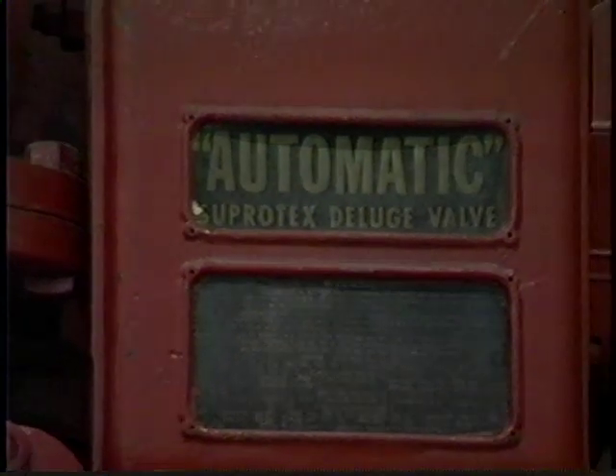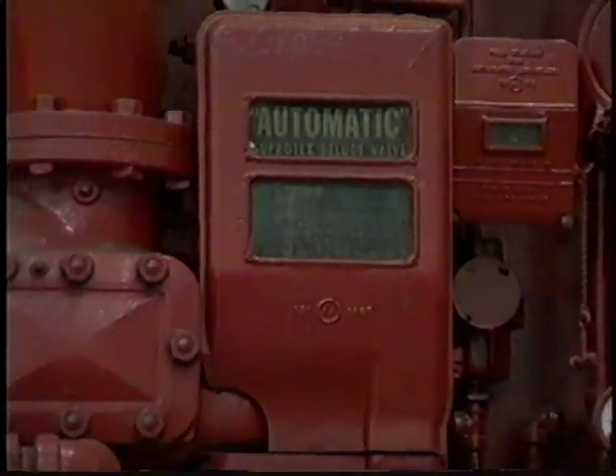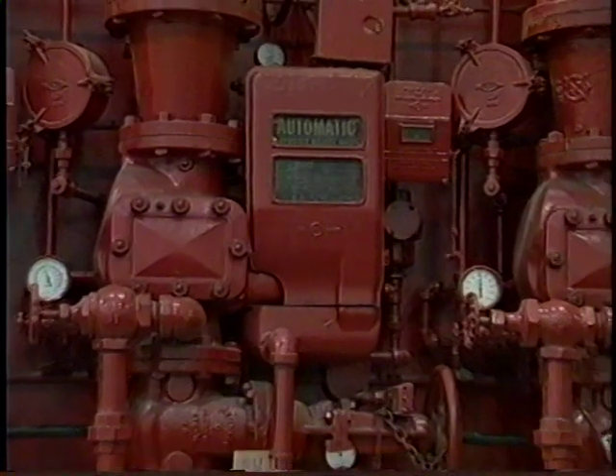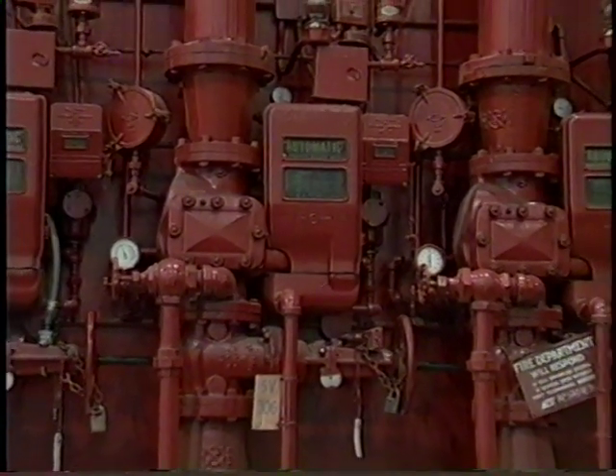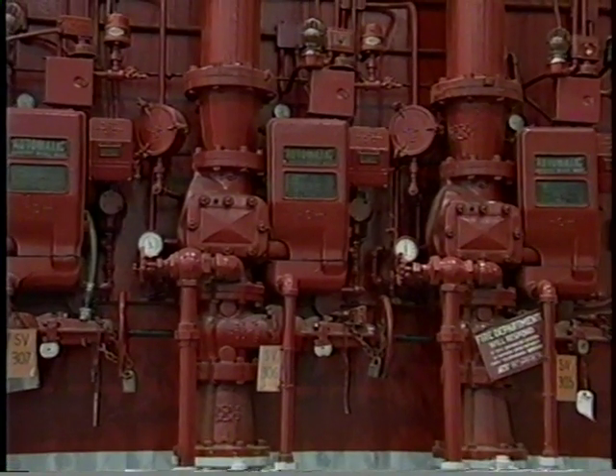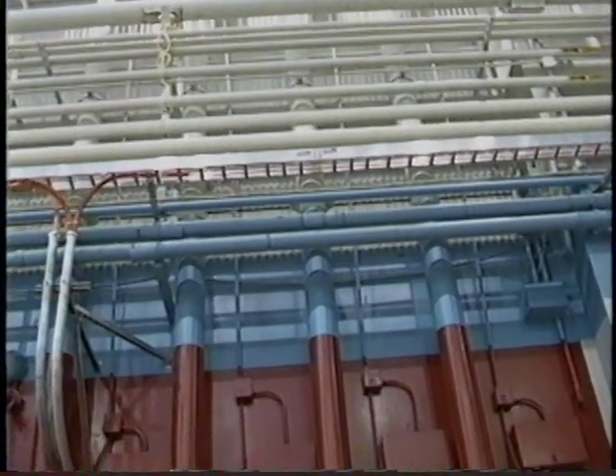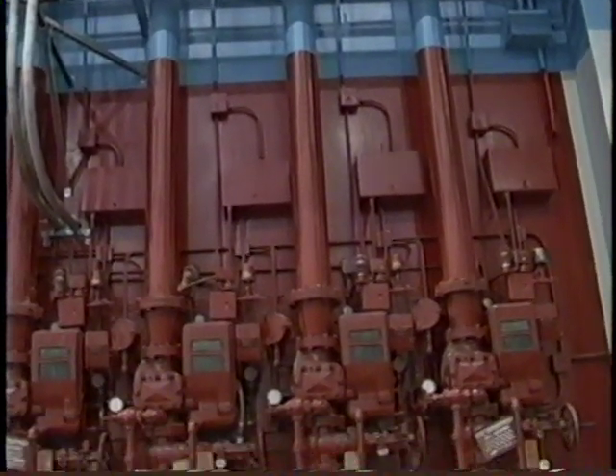Sprinklers in a deluge system do not have heat-responsive elements, so a separate detection system is necessary. This detection system is connected to a tripping device that activates the flow of water to the sprinklers.